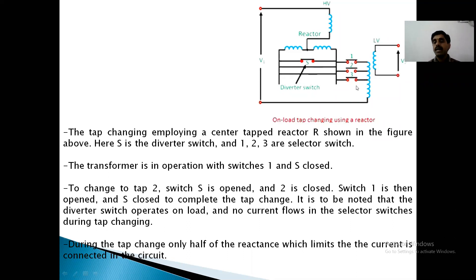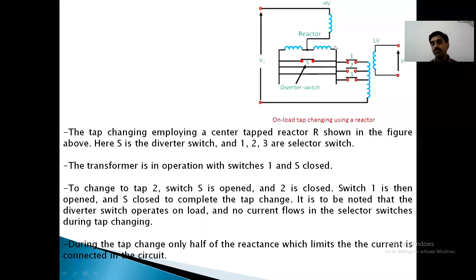What we observe here is that the diverter switch operates on load and no current flows in the selector switches during tap changing. When changing from switch 1 to switch 2, there should not be any current flow in the selector, which is why we open the diverter switch first. Half of the reactor is included, which limits the current connected to the circuit — that is the use of the reactor.